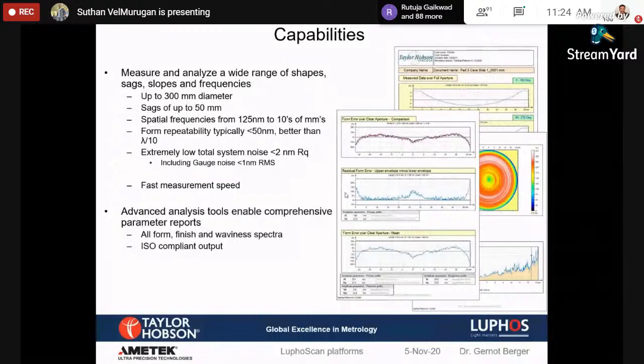We follow the roughness parameters or the form error analysis parameters, the algorithms we use in our Taylor Hobson defined software. We follow the ISO standards, and which standard we are following is a part of our report. We can change it; for example, if a Japanese customer is trying to use the JIS standard, in the software we can switch over from the ISO standard to the Japanese standard, and then the analysis or algorithm will automatically change as per that standard. Similarly, if somebody from Europe wants to follow the VDI standard or their German standard, the software is very flexible. We can change the standard according to the user requirement.